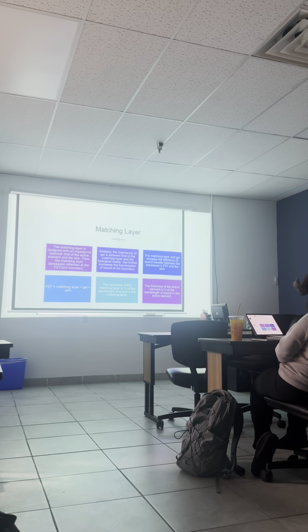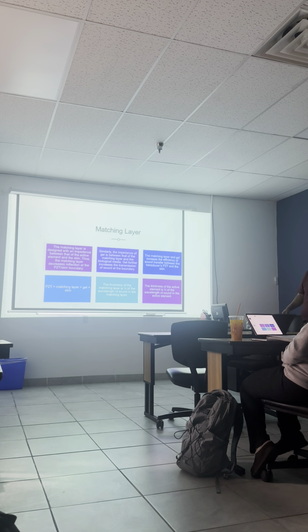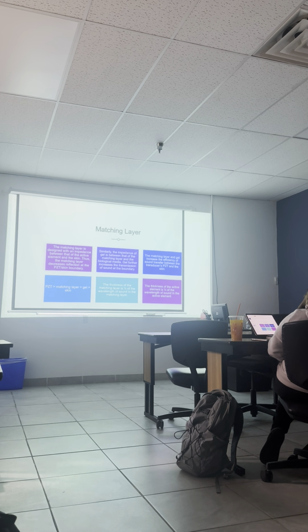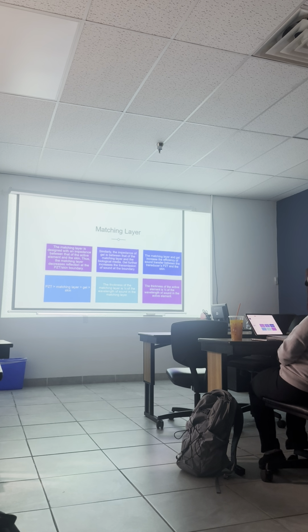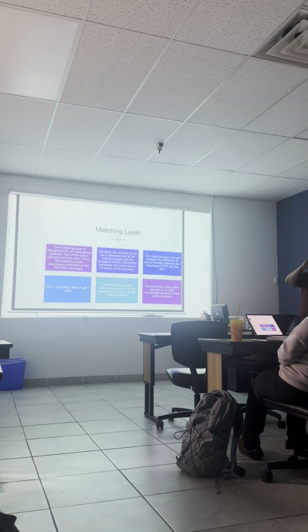Okay, so what do we use in between the matching layer and the skin? Gel. Why? Because it helps transmission of sound into the skin. Exactly. It helps the propagation of sound into the patient's body. And why do we need propagation of sound into the patient's body? To be able to see, or listen. We need propagation of mechanical energy or sound into the patient's body to receive echoes. Those echoes are then received by the transducer, interpreted, and displayed as an image on the screen.